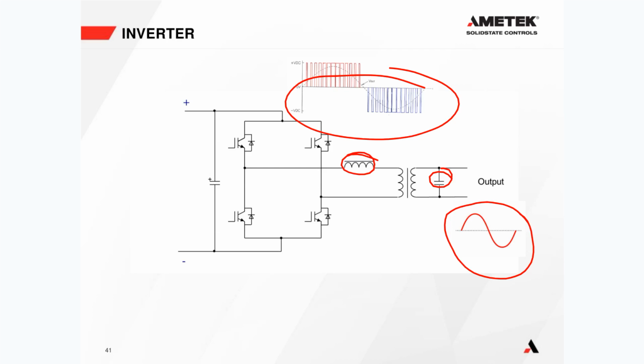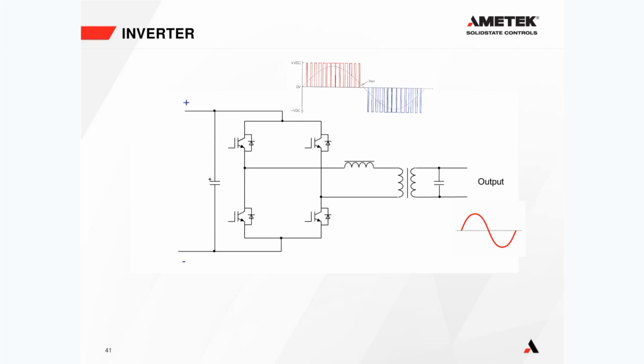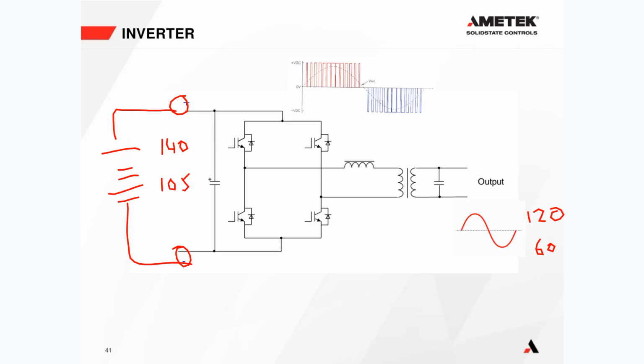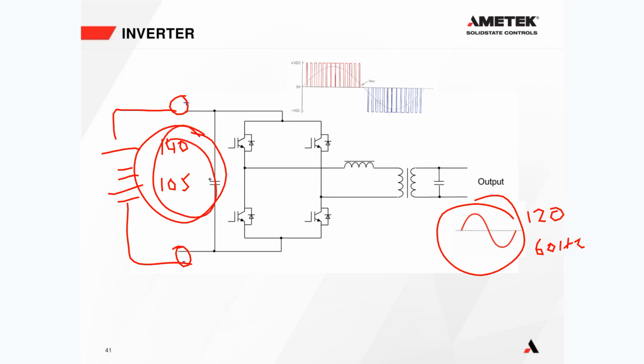But that's what the inverter's job is. It is converting this positive and negative, which comes from the battery, which we know is going to be for lead acid, 60 cells, between 140 volts and 105 volts. This output is going to be 120 volts, 60 hertz, at all parameters between 140 and 105. This output is not going to change. It's going to be a beautiful sine wave for all of these points between 140 and 105 on the DC.